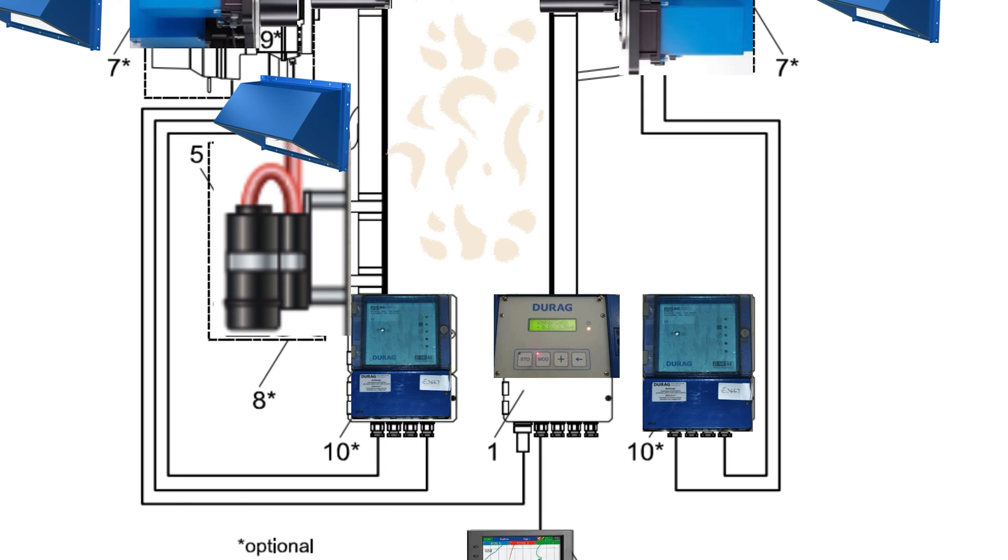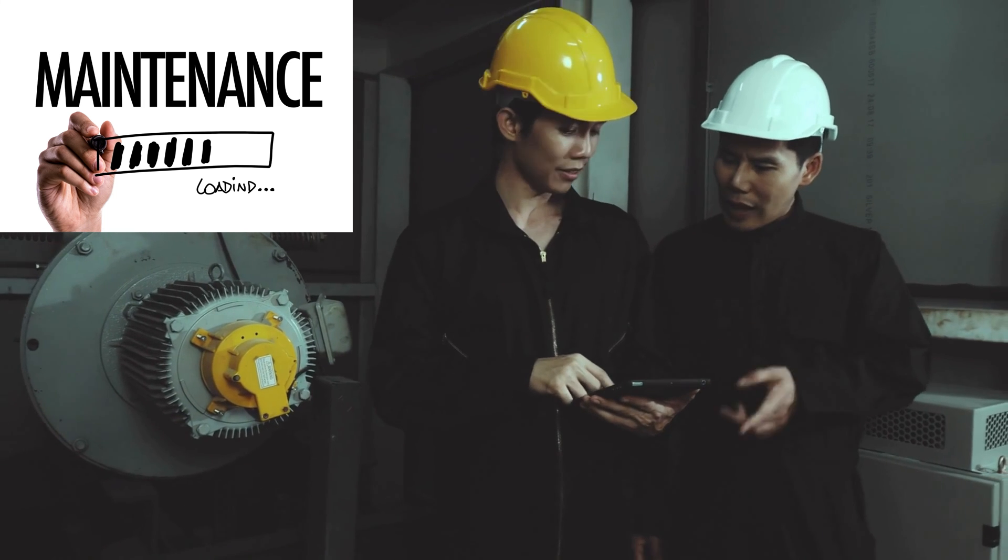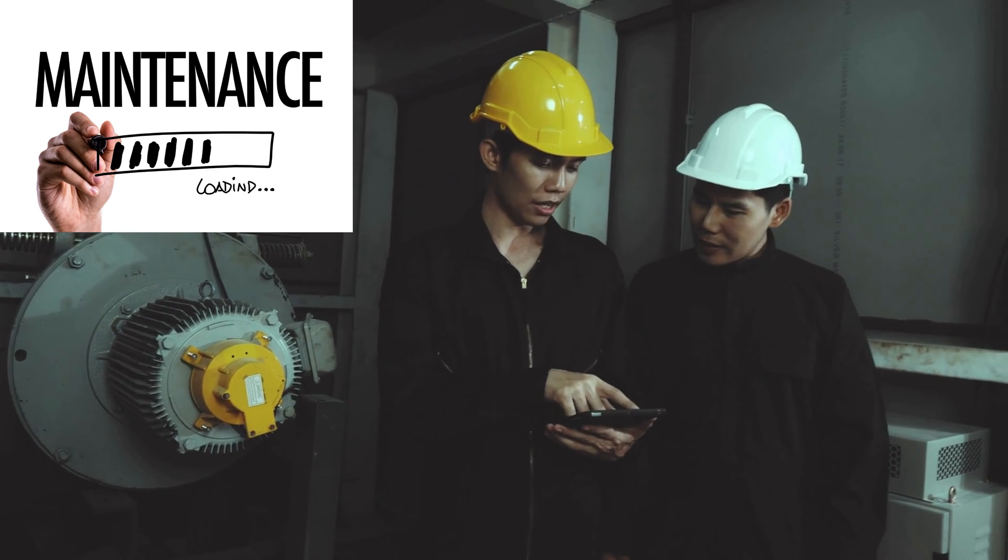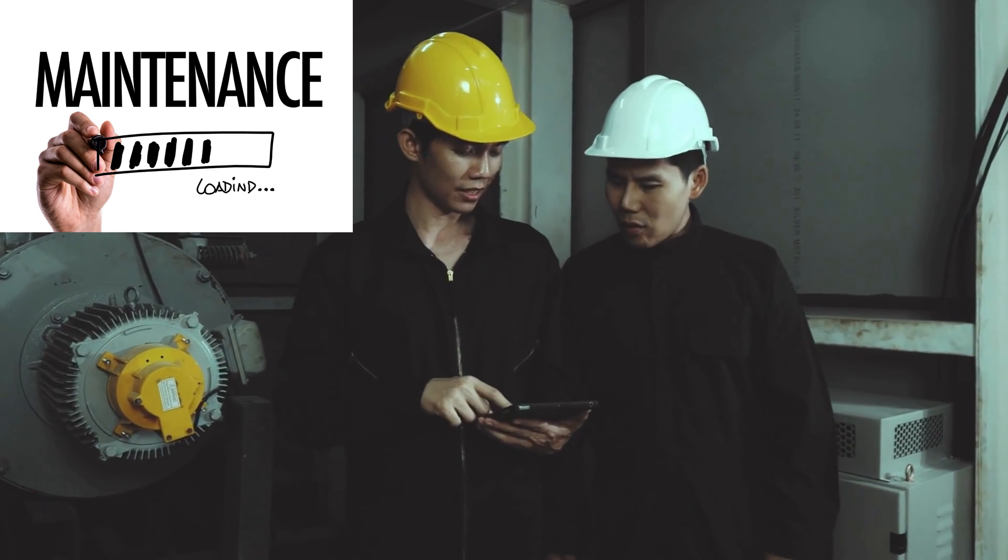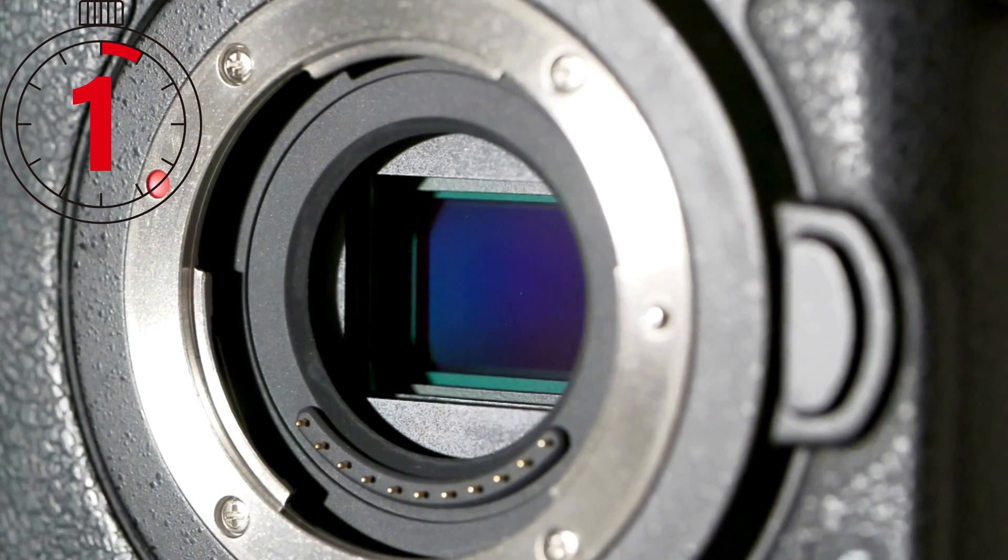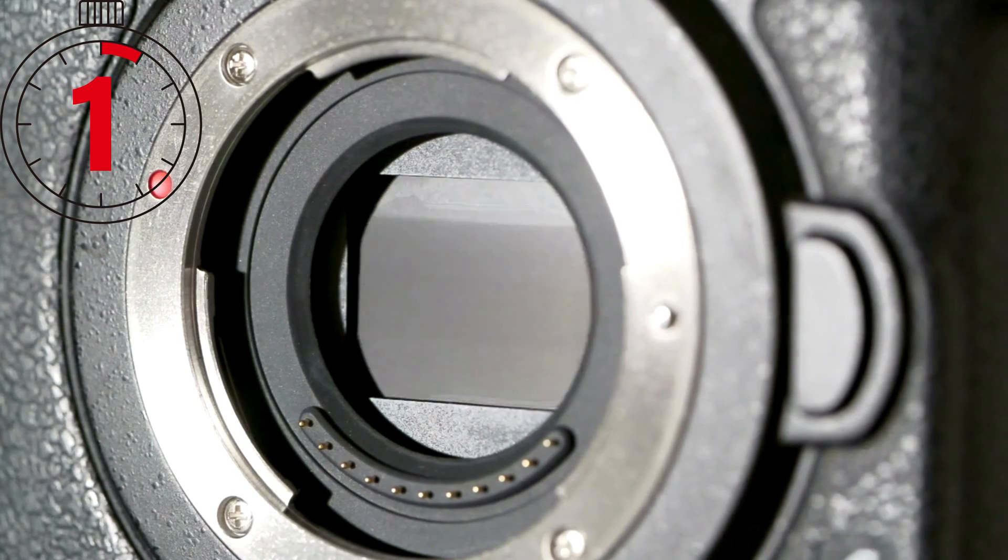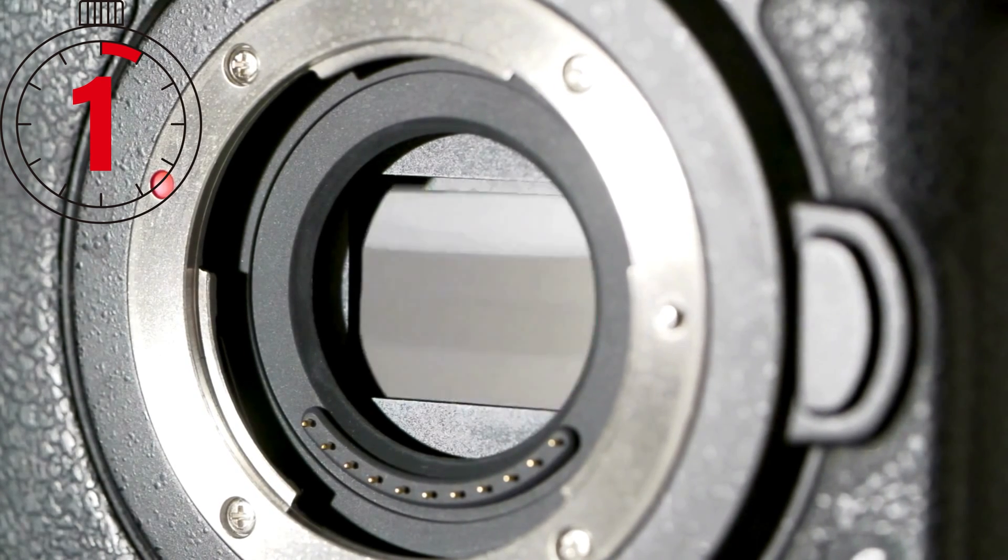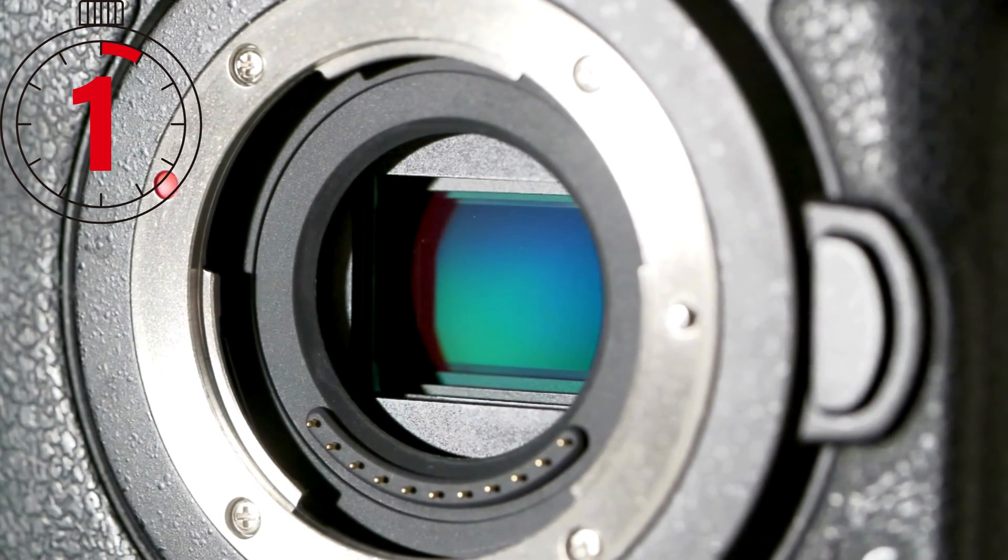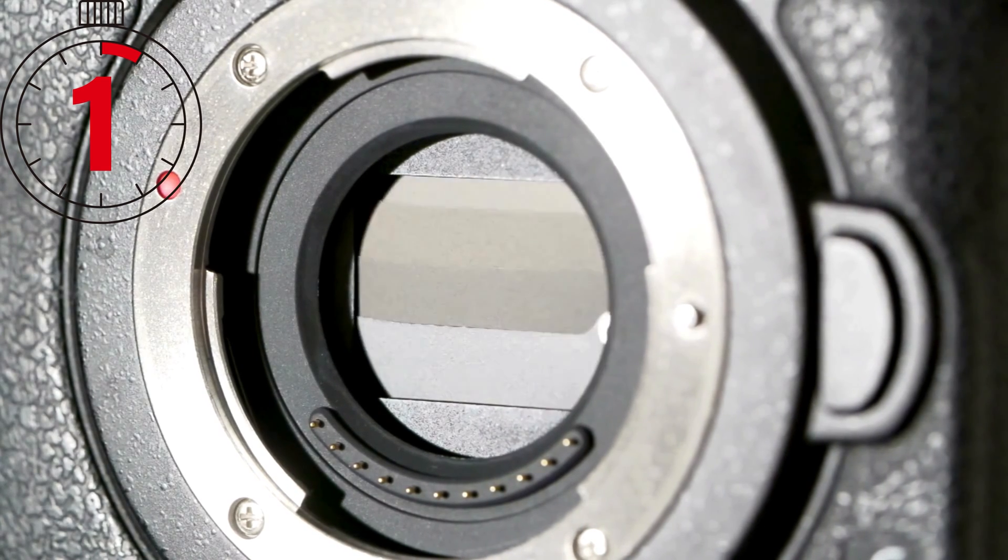Following points to be checked as routine maintenance of system. Cycle can be minimum one or three months depending on site condition. First, clean transceiver reflector window and zero point reflector with soft cloth. Water, alcohol, or glass cleaner can be used to clean optics. Second, clean external parts of unit.